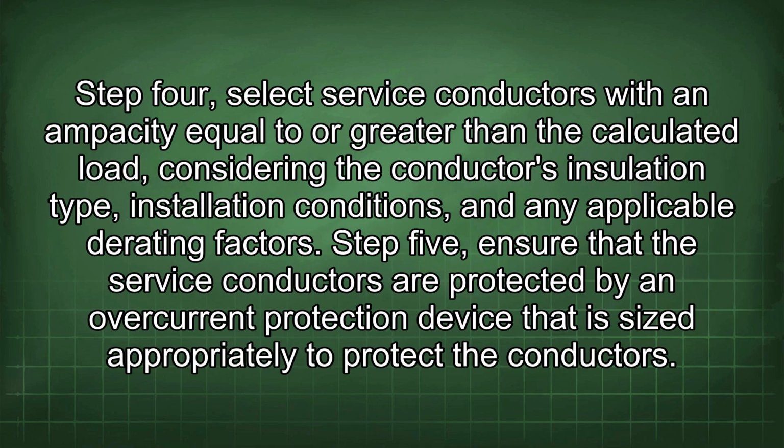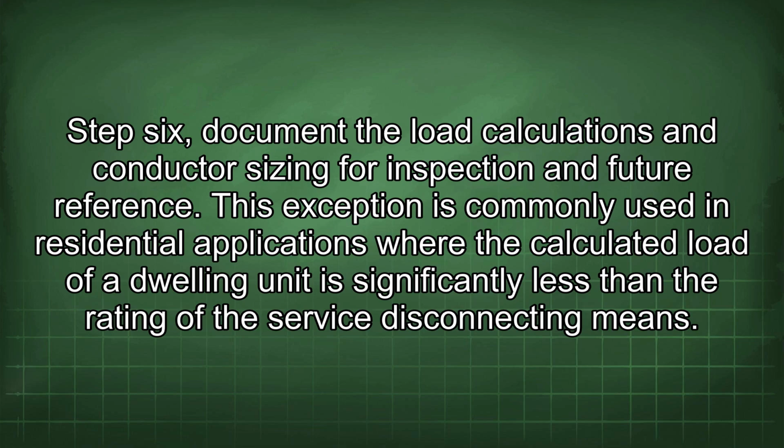Step 4. Select service conductors with an ampacity equal to or greater than the calculated load, considering the conductor's insulation type, installation conditions, and any applicable derating factors. Step 5. Ensure that the service conductors are protected by an overcurrent protection device that is sized appropriately to protect the conductors. Step 6. Document the load calculations and conductor sizing for inspection and future reference.